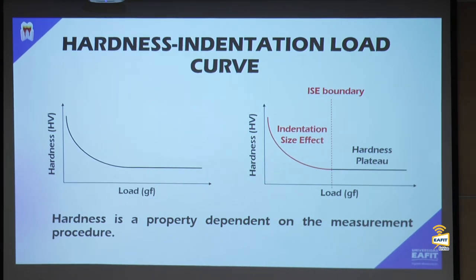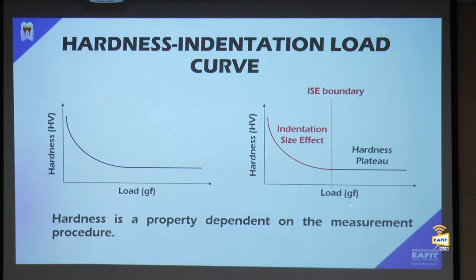When you analyze all these loads, you'll see a curved region — this is the indentation size effect (ISE). Due to elastic recovery and the small energy applied at low loads, the material recovers in a non-homogeneous way, making hardness dependent on the measurement process. You must cover all loads and find the plateau where values stabilize. Beyond the plateau, excessive energy is dissipated through crack propagation, damaging the sample.